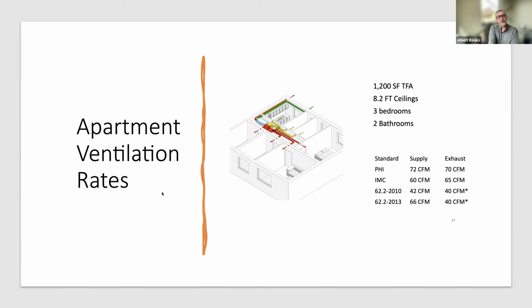Would it be bad to choose 42 CFM, 62.2-2010, 42 and 40 compared to Passive House 72 and 70? If we used efficient equipment with good heat recovery, there wouldn't be an energy impact. If we gave the building a little more fresh air, would that be bad for the occupants? Probably not. There is a range, and most of these systems will give you some guidance on how to prevent that, saying if we put in 2 times the amount of airflow, like if we doubled the Passive House to 140, essentially then, depending on where we are, we would tend to dry out the building because we'd be pushing all the moisture out at a rate that generally occupancy won't recover by human occupation and basically the outside conditions of the building.